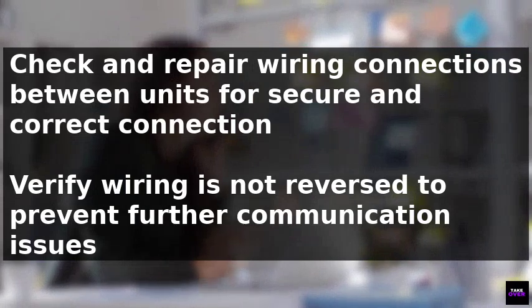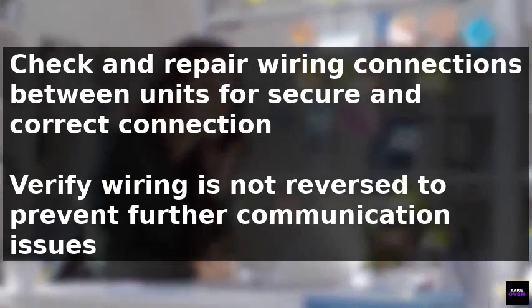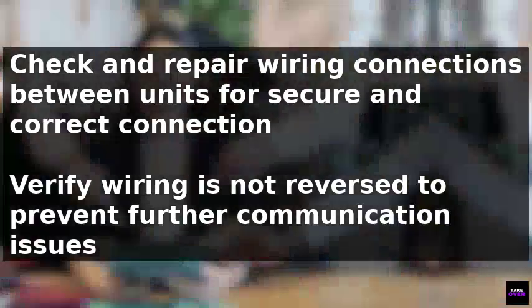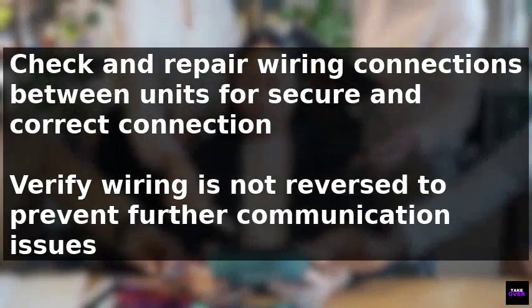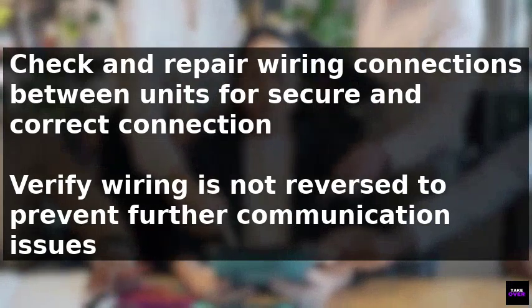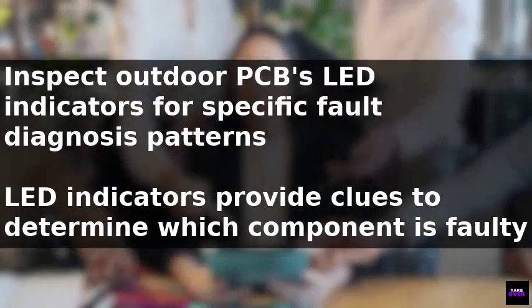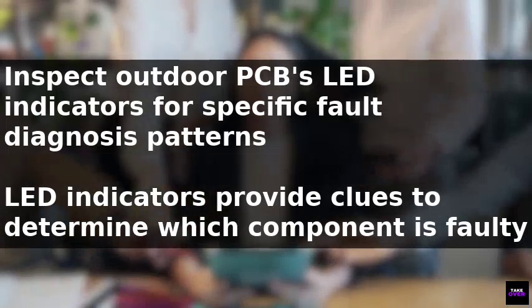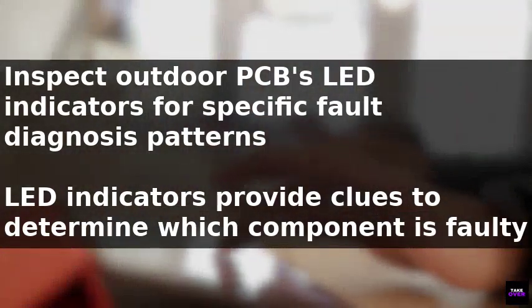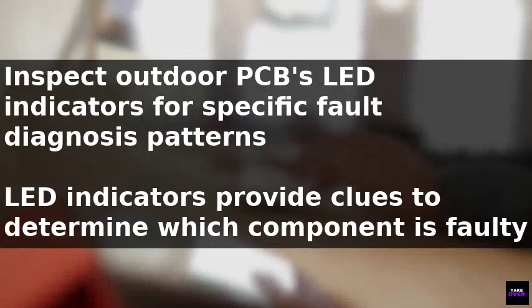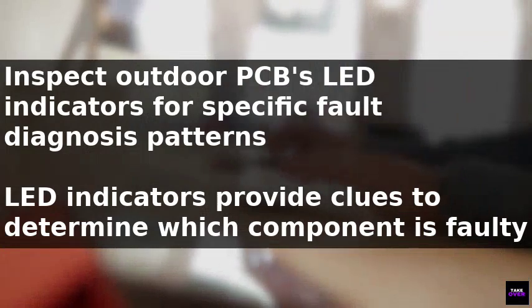To resolve the issue, start by checking and repairing the wiring connections between the two units, ensuring they are securely connected and not reversed. If the wiring is not the problem, inspect the outdoor PCB's LED indicators. If LED 1 is off and LED 2 is on, the outdoor PCB is defective and needs replacement.